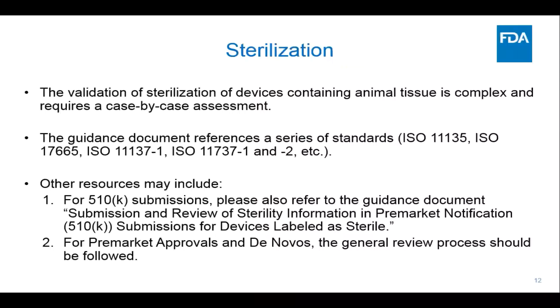One of the concerns of using animal tissue as a material in medical devices is the potential for viral contamination, which may negatively affect the patient. Therefore, to ensure adequate inactivation and removal of the potential viruses present in the animal source, the processing methods and sterilization techniques used to manufacture the device should be assessed, which are referred to as viral validation studies in the guidance document. In the pre-market submission, the sponsor may either provide test reports for each manufacturing step identified to contribute to the viral inactivation or to the reduction in the viral load, or provide literature-based evidence for each identified manufacturing step.